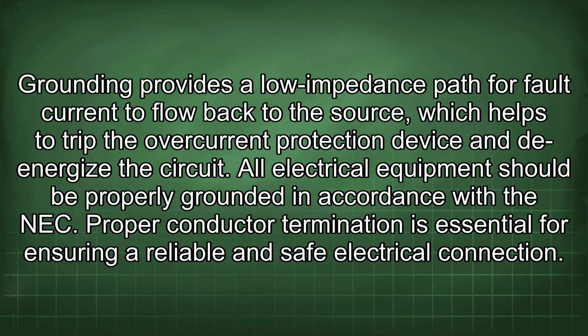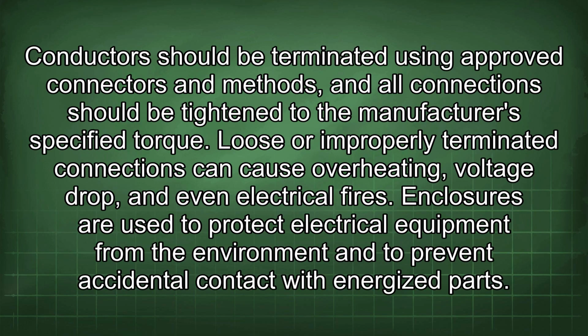Proper conductor termination is essential for ensuring a reliable and safe electrical connection. Conductors should be terminated using approved connectors and methods, and all connections should be tightened to the manufacturer's specified torque. Loose or improperly terminated connections can cause overheating, voltage drop, and even electrical fires.